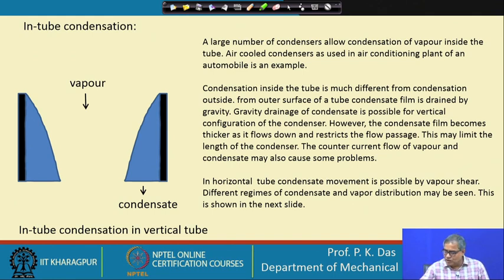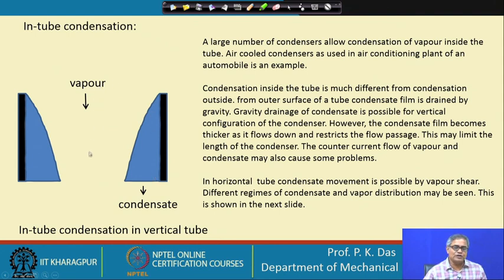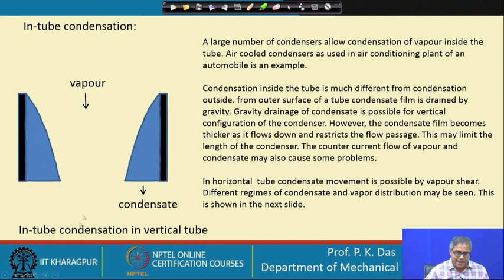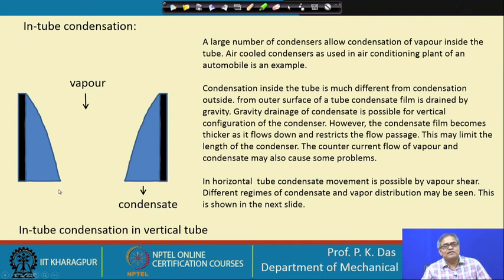In this particular case, liquid is draining in the downward direction, which is good. At the same time, vapour is also flowing downward, so vapour pushes the liquid downward — this is a favourable configuration. In some designs, the vapour goes upward while the condensate must come downward, and though such configurations exist, they may give some problems.